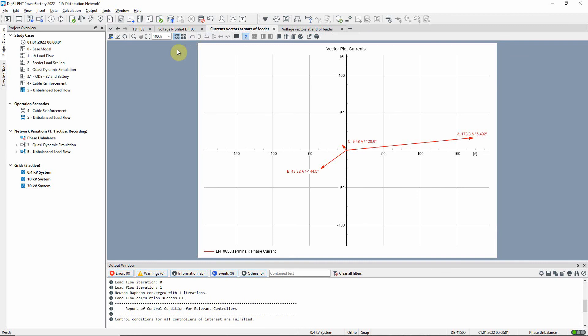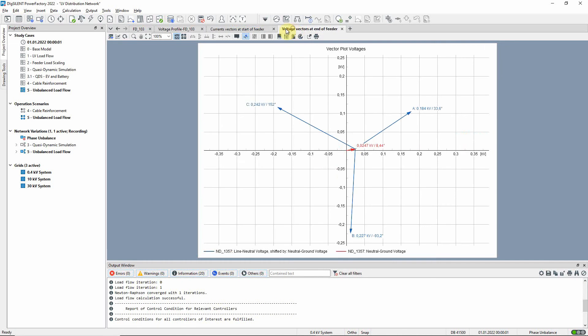Looking at the vector plots, it is clear that the currents are very unbalanced and there is also a high neutral to earth voltage.